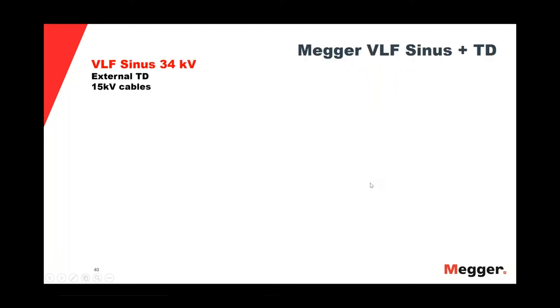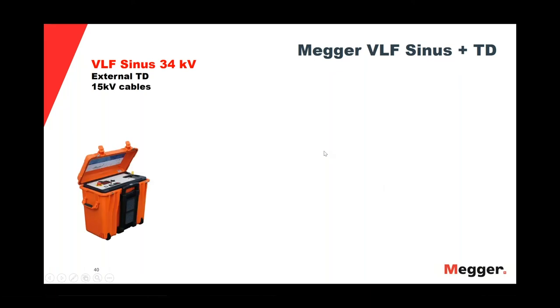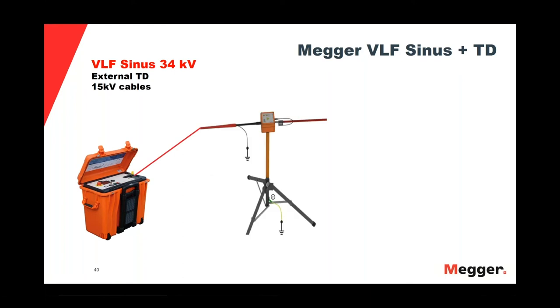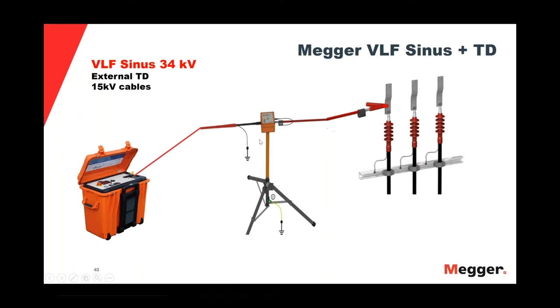For finish, I would like to talk about the VLF units that we have at Megger. The first one I would like to talk about is the VLF Sinus 34. This unit has an external tan delta attachment, and we use this VLF to test cables up to 15 kV. And as I said, we have an external tan delta attachment, okay? And we can see it, the external tan delta. This is the smallest VLF unit we have in Megger.